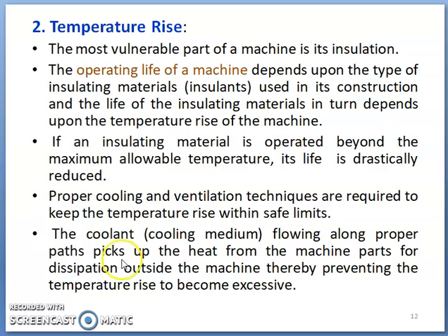The cooling medium flowing along proper paths picks up heat from the machine parts for dissipation outside the machine, thereby preventing temperature rise from becoming excessive. There are three modes of heat dissipation: conduction, convection, and radiation. Depending upon the type of cooling techniques used, if the rate of temperature rise and the rate of temperature dissipation are thermally balanced — if thermal equilibrium is achieved — then the designer can go for higher outputs for a given class of insulation material and specific electric and magnetic loading.